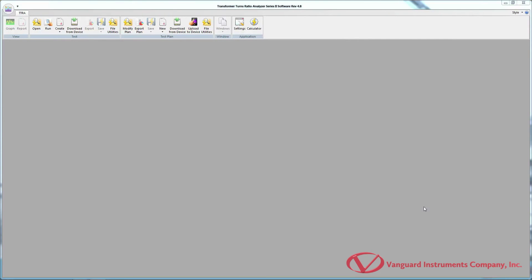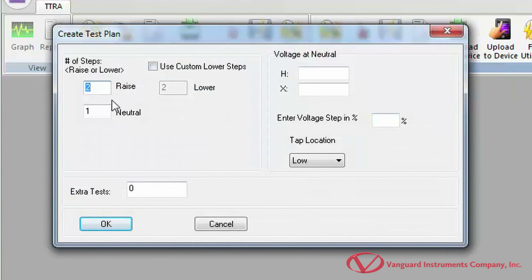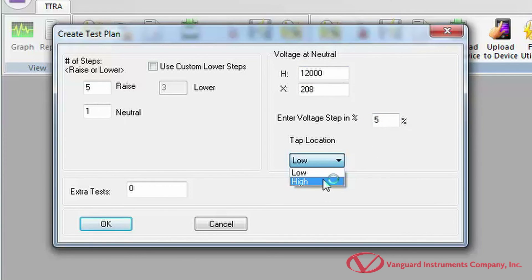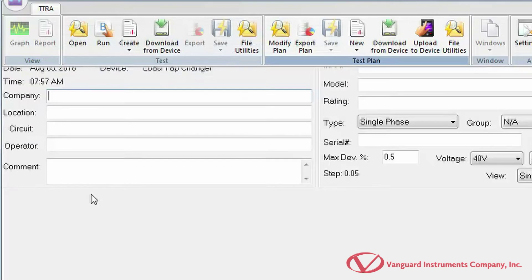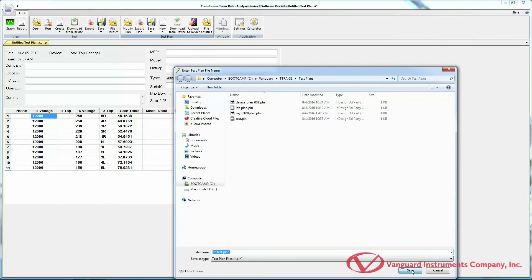Creating a test plan for a load tap changer is almost the same as for a voltage regulator. Click the arrow below the New icon in the Test Plan command group and select Load Tap Changer. Enter the number of raise steps and neutrals. If the lower steps differ from the raise steps, check Use Custom Lower Steps and enter the number. Enter the H and X voltage values at neutral and the voltage step in percent, then select the tap location and click OK. Enter relevant header information, select the test voltage and device type. After making all necessary changes, don't forget to save your test plan.